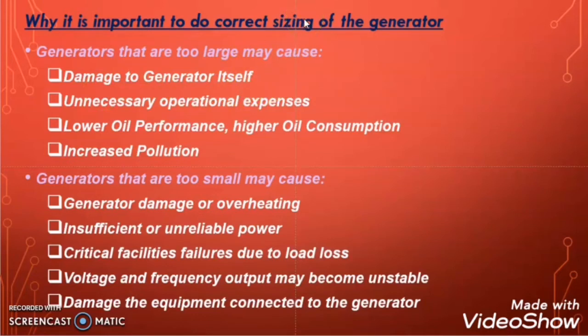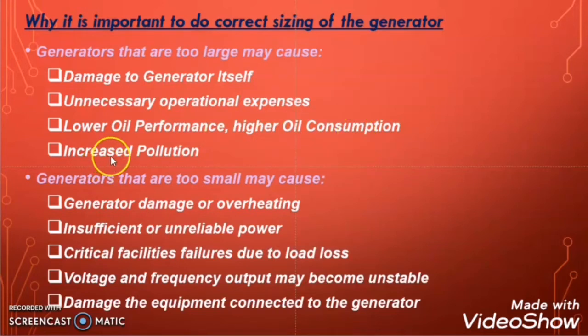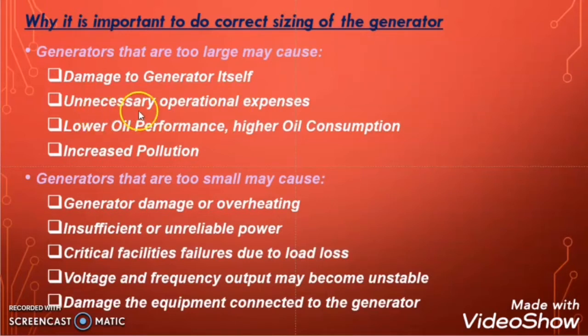When the generator is oversized, the fuel combustion is partial — so lower oil performance and higher oil consumption result. As the fuel is burning partially, it will create more smoke and more soot, increasing pollution. Also, for a little load you have to operate a bigger generator, which will definitely increase your operational expenses unnecessarily. These are the disadvantages of oversizing a diesel generator.